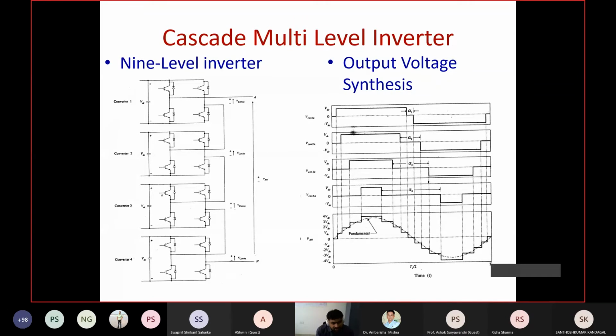So when you want to directly interface such generated power to the grid, you already have isolated voltage sources available with you. When you connect such small scale renewable generated voltages to each converter 1, 2, 3 and 4, you can generate a high voltage. In this renewable application, you need not use a transformer in the DC side to give isolated DC voltages. You already have isolated DC links, and you can directly connect those to your cascaded inverter to generate a high voltage in the AC side.